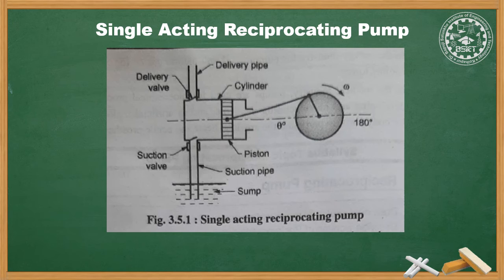When a graph is plotted between discharge and crank rotation, it shows that during 0 to 180 degrees (suction stroke) there is no discharge. From 180 to 360 degrees, discharge gradually increases until 270 degrees, then decreases. This shows that the discharge through a single acting pump is intermittent — that is, not regular. The single acting pump has a single suction and delivery pipe.